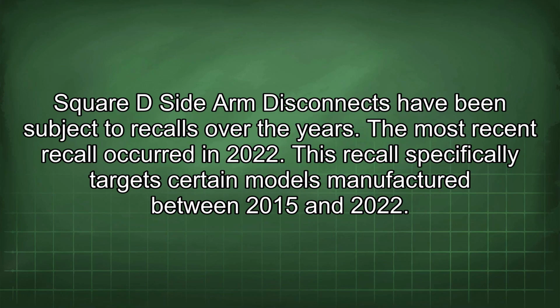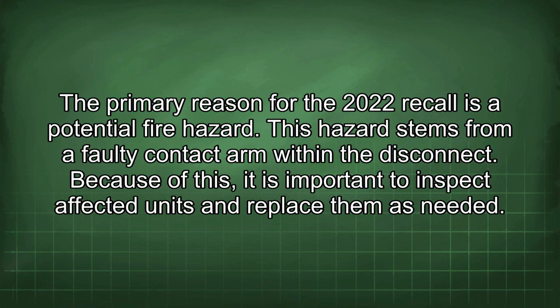Square D sidearm disconnects have been subject to recalls over the years. The most recent recall occurred in 2022. This recall specifically targets certain models manufactured between 2015 and 2022. The primary reason for the 2022 recall is a potential fire hazard. This hazard stems from a faulty contact arm within the disconnect. Because of this, it is important to inspect affected units and replace them as needed.